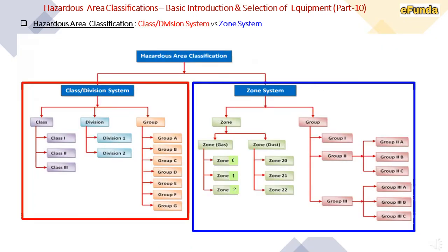The Class Division System versus Zone System: the class division system consists of Class 1, Class 2, Class 3; divisions are Division 1 and Division 2; and groups are Group A, B, C, D, E, F, G. The zone system has zones for gas — Zone 0, Zone 1, Zone 2 — and zones for dust — Zone 20, Zone 21, Zone 22. Groups are classified into Group 1, Group 2 and Group 3, with Group 2 further divided into 2A, 2B, 2C and Group 3 into 3A, 3B, 3C.